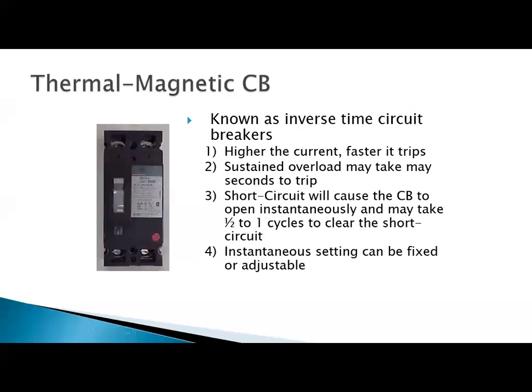Now we're going to get into breakers that might be a little bit larger than the molded case breaker. So this one here, thermomagnetic circuit breaker, also known as inverse time. What does that really mean? When that current skyrockets up because we have a short circuit or ground fault, the clearing time is going to be much quicker. The magnetic portion of the breaker is going to act much quicker than the thermal portion of the breaker. On a short circuit or a ground fault, we could open up that circuit in a half to one cycle, so right around 0.01 hundredths of a second. And these can also be adjusted.